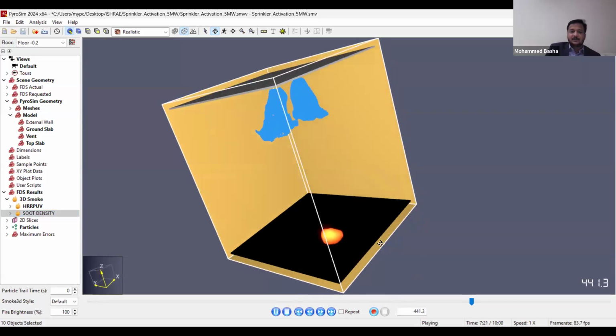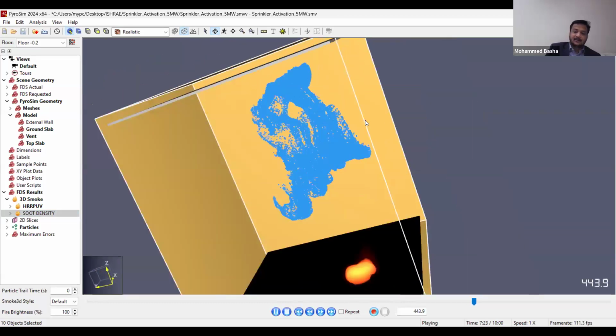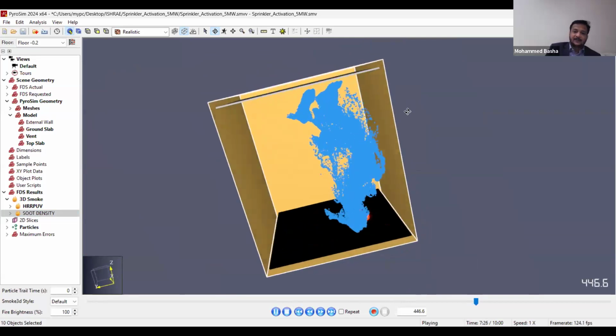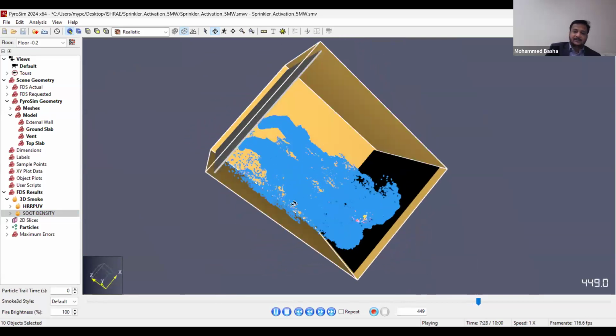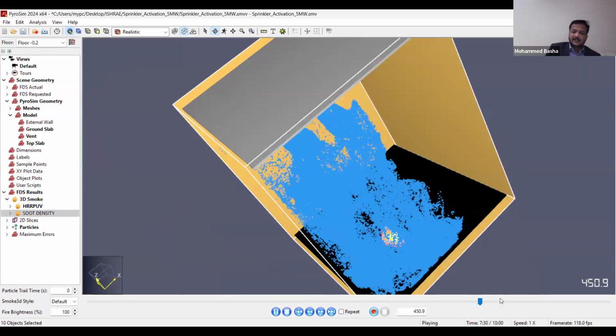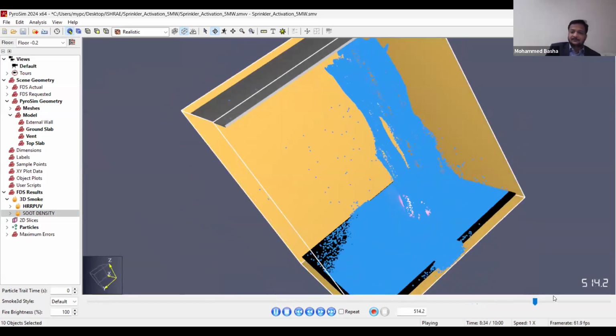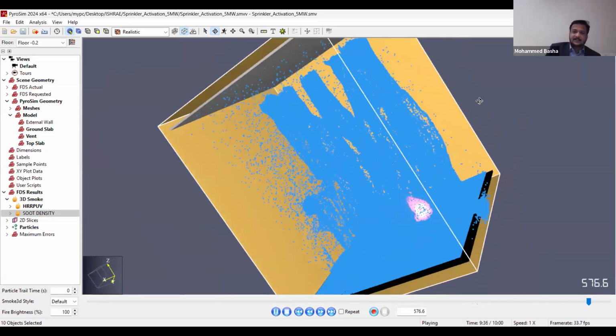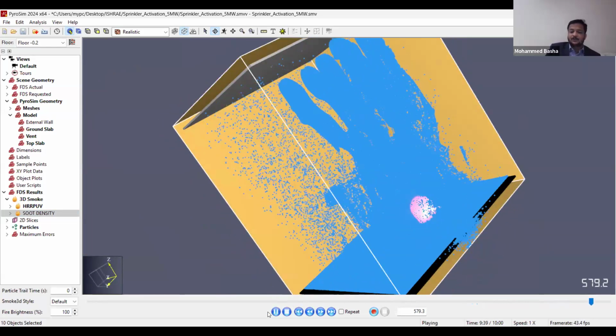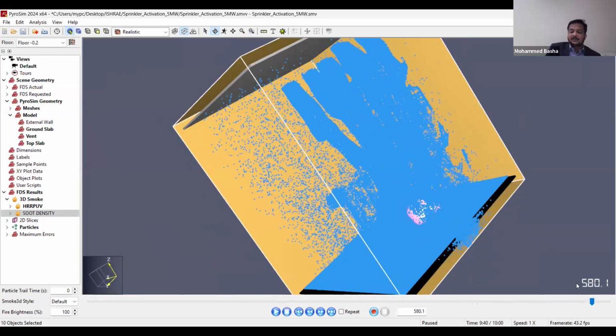So just assume, see, now 2 sprinklers got activated. Okay, now when the time goes further, 3, so you can see around 4 sprinklers will get activated at 500 seconds basically. So at 550 seconds, around 4 sprinklers got activated. So I should take the HRR corresponding to 550 seconds. And I need to have a CFD simulation also to ensure that at that 550 seconds, where is my smoke layer? It should not be full. If it is full, then there is no point in designing a smoke management system.